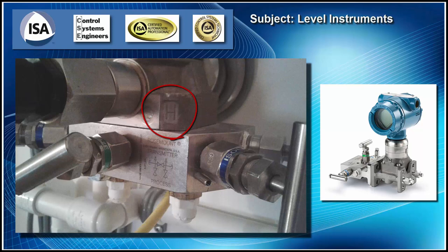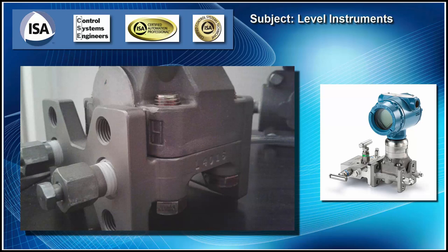And here we have a three-valve manifold. On the three-valve manifold, you can see that we have a drain in the side. So you open up this drain breather, you unscrew it, and you screw in there, and that's where you actually do your calibration. Now, notice this is a coplanar because the tubes would connect to the bottom where these white fittings are. This is where your tube would normally come in. Now here we're seeing a biplanar because it comes in horizontally, and all we have to do is take our vents out of the back and we can plug in there with our pressure pump, and we can pump this up to the pressure we want.